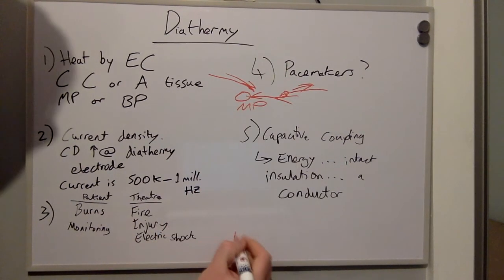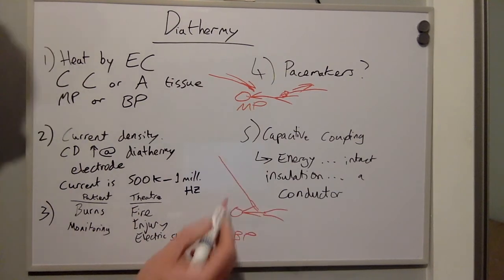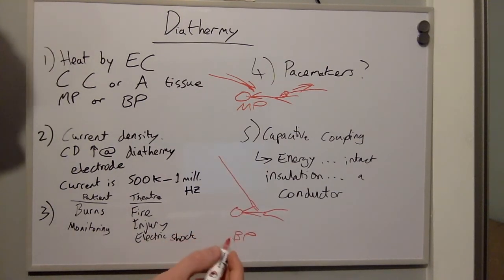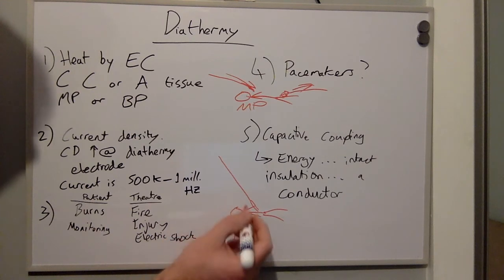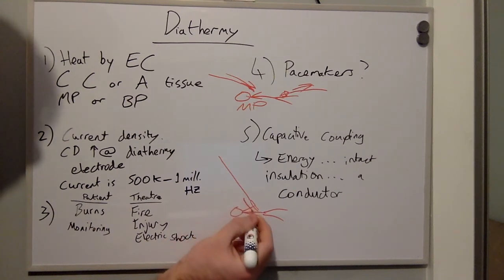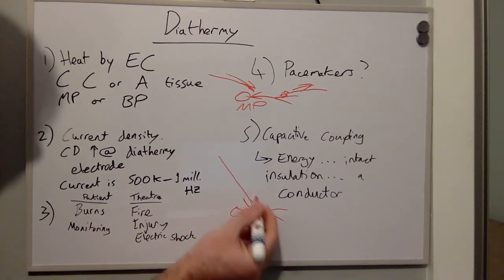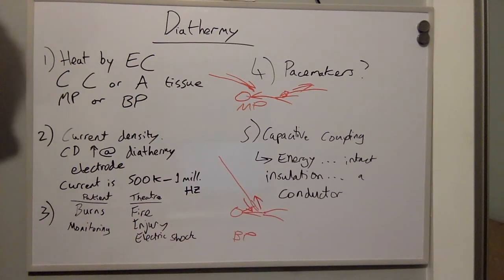With bipolar diathermy, the tip of the diathermy is used to complete the circuit. So the current that flows to the patient and the current that flows away from the patient is all done through the diathermy tip.